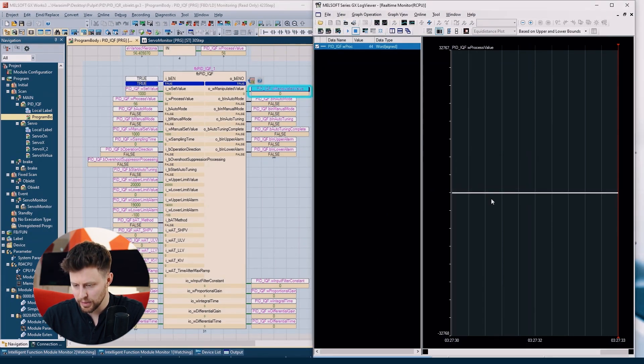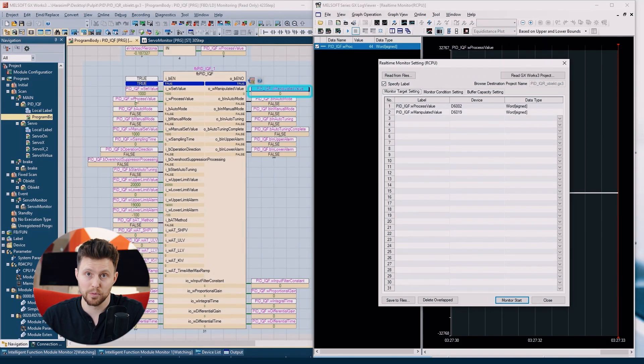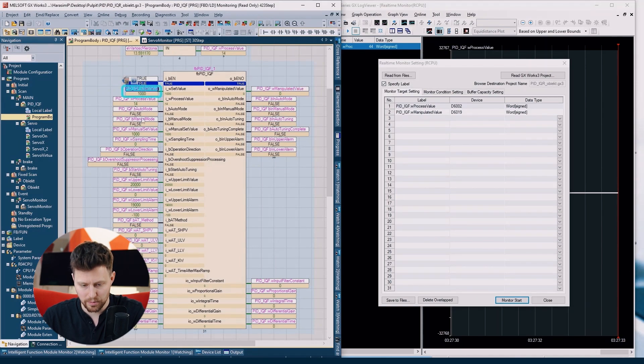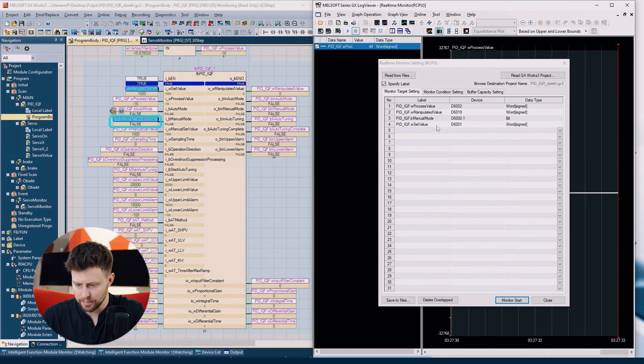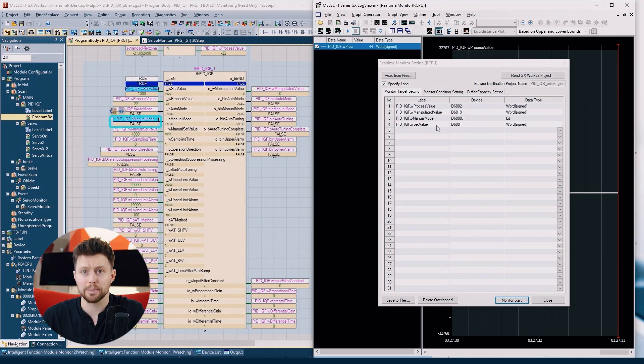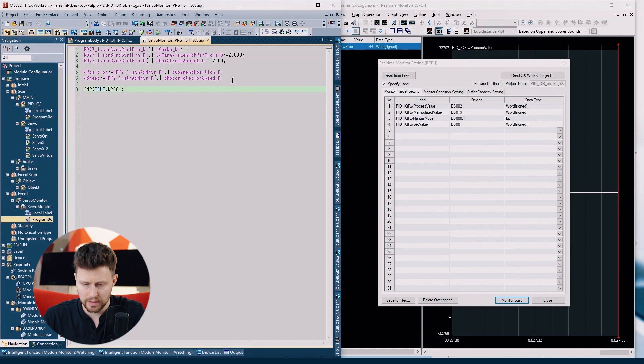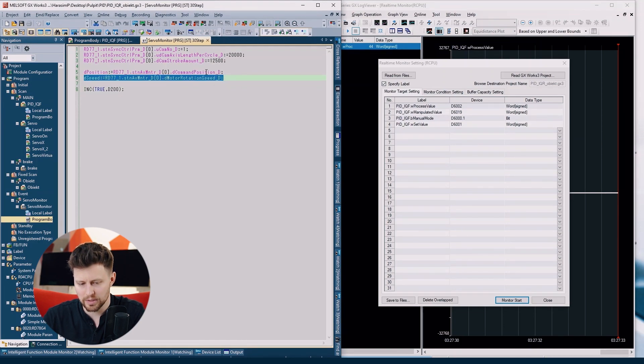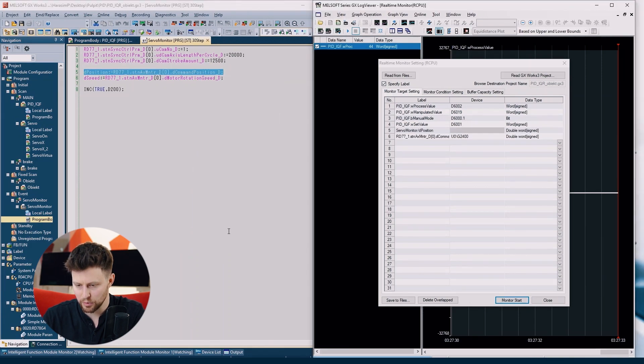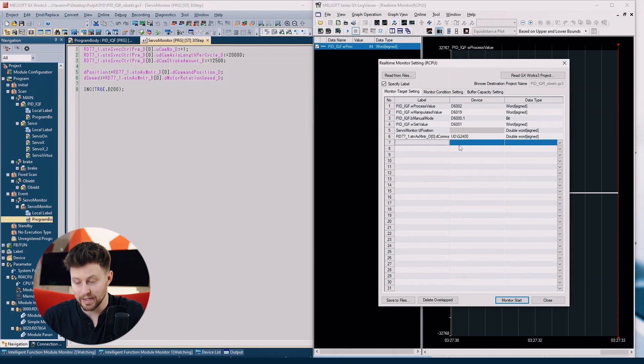We have to stop our monitor to add more variables. Let's use this time and add even multiple variables at once — we can choose two variables and add them at the same time. If we have an ST program, we can even select the whole line in the code and all the variables in that line will be added automatically to our real-time monitor. We can also add values manually by label or by direct address.